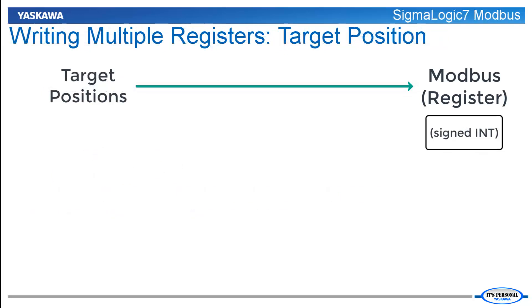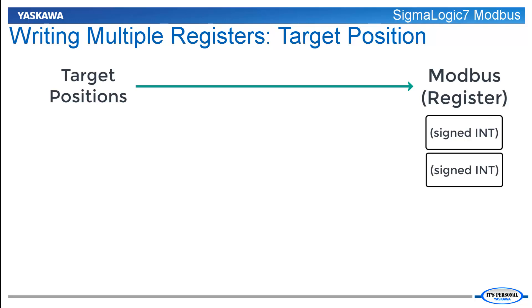Commanding target positions will require more data manipulation. The range of target positions is too large to fit within one 16-bit register; therefore, the user must split the number into two consecutive signed integers and write them to registers starting at 40033. Register 40033 will contain the least significant word, also known as the low word, and register 40034 will contain the most significant word, known as the high word.